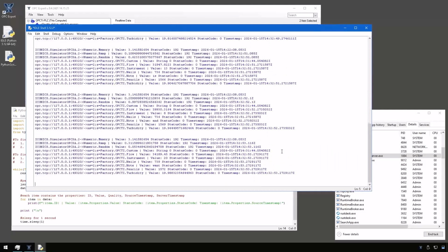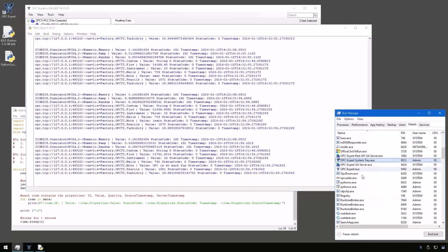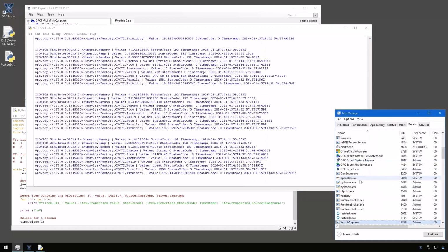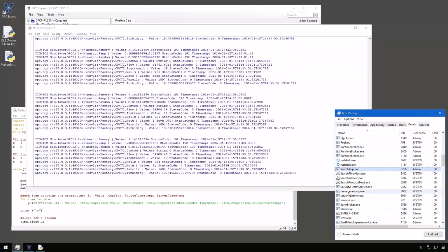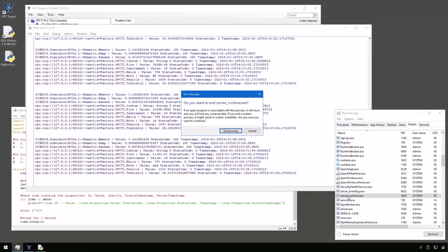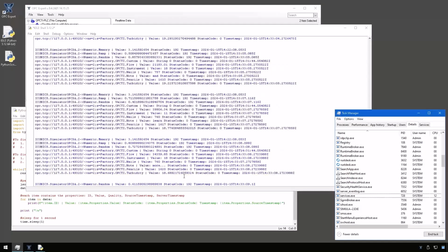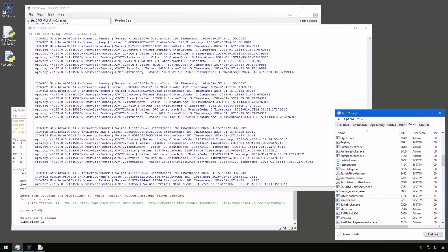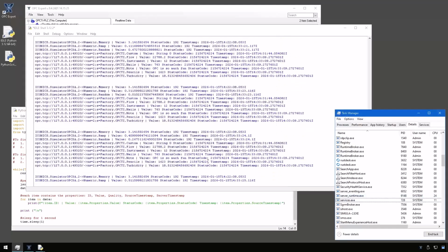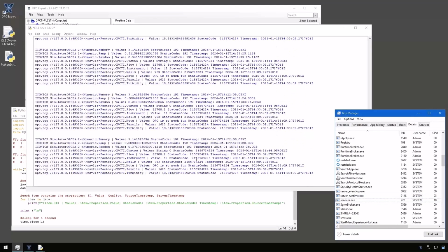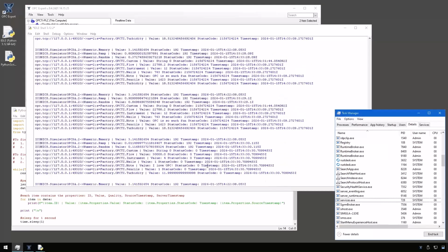Now, what's quite interesting is let's go ahead and create a problem. I will go to the Kepware server, which is the UA server, just as an example, server underscore runtime, and I will just kill it end process. And now you can see the status code is different until it reconnects. See, the status code is no longer 0. And automatically, the connection will be reestablished. The server restarts. And in just a little bit, we're going to get new data again. There we go. Status code is 0 again.